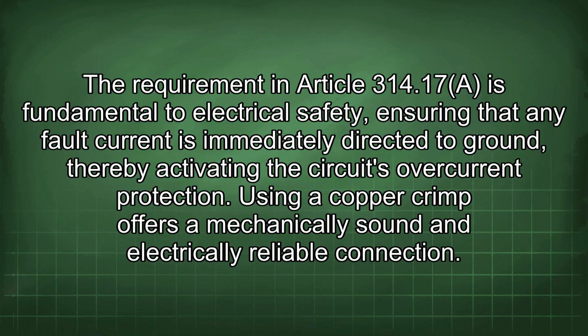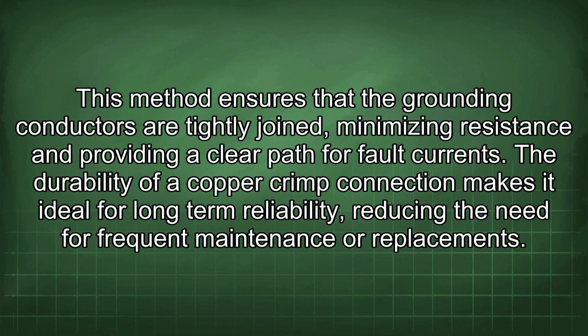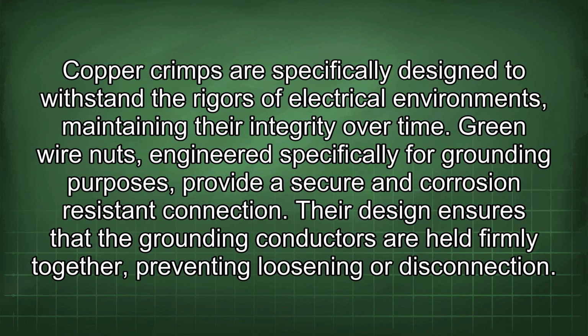Using a copper crimp offers a mechanically sound and electrically reliable connection. This method ensures that the grounding conductors are tightly joined, minimizing resistance and providing a clear path for fault currents. The durability of a copper crimp connection makes it ideal for long-term reliability, reducing the need for frequent maintenance or replacements. Copper crimps are specifically designed to withstand the rigors of electrical environments, maintaining their integrity over time.